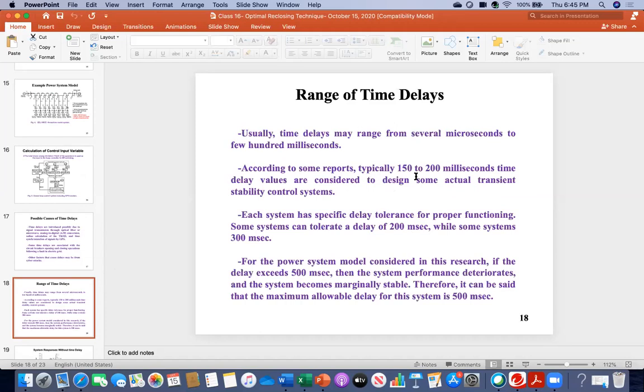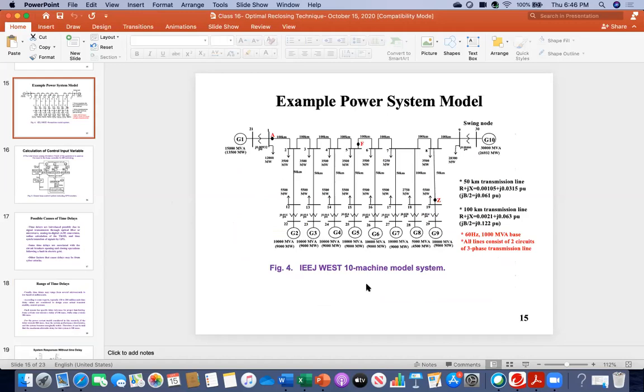As I said, if you see the second bullet, some report says, probably they have investigated a subsystem, they said, okay, it should be around this range. That is enough to design some actual transient stability control means. But then I have seen some other report with a much higher value. And then I myself did some analysis for this system. I went up to 500 millisecond. And I noticed if I exceed this number, then the system becomes unstable. So then I concluded that for this system, the delay margin is 500 millisecond.